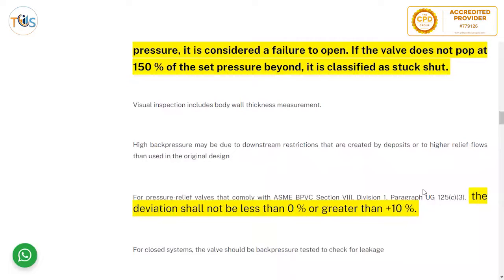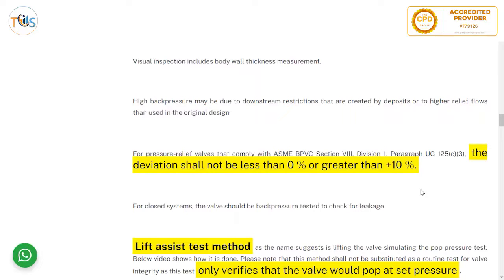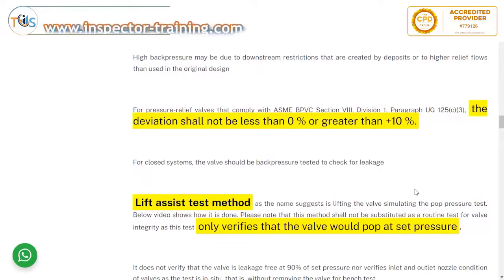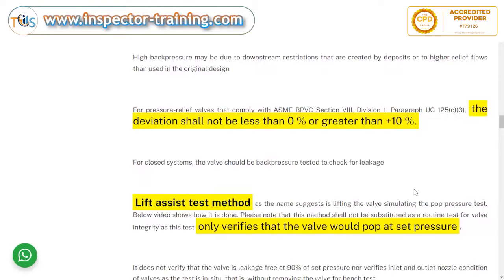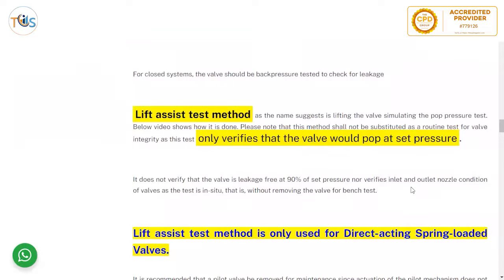Valve inspection includes body wall thickness measurement. High back pressure may be due to downstream restrictions created by deposits or higher relief flows than used in the original design. For pressure relief valves that comply with ASME BPVC Section 8, Division 1, paragraph UG-125, the deviation shall not be less than 0% or greater than 10% — meaning it should open no earlier than the maximum allowable working pressure (MAWP) and no later than 1.1 times the MAWP.